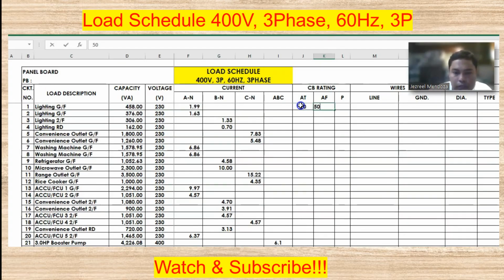Ampere frame, let's use 50. Okay, this is very important. If we're using line to neutral, we're using 1-pole circuit breaker. If we're using 2-pole, that is 230 volts line to line. That's 2-pole yon. Pag line to neutral, that is 1-pole, 1 line plus neutral.